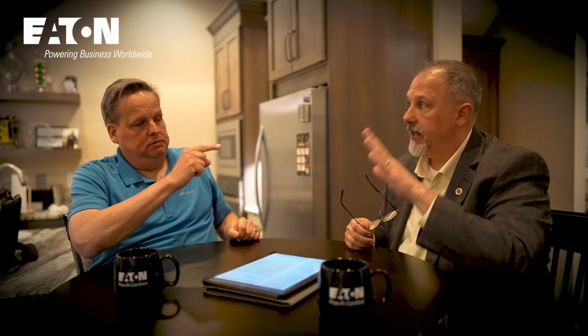Yes. So this picks up, like he says, I don't care if it's hardwired or cord and plug connected, but this list of appliances is important anywhere. It doesn't say if it's in a dwelling unit. It doesn't tell you if it's in a commercial building. I don't care where these appliances are located. You need to have that outlet GFCI protected. Can't be in the cord of the appliance. It has to be protected. We didn't make that distinction in C. Notice now we are away from occupancy types. Yeah. C, D, these are independent of occupancy. That's right. So very important to know, not driven off of the occupancy.